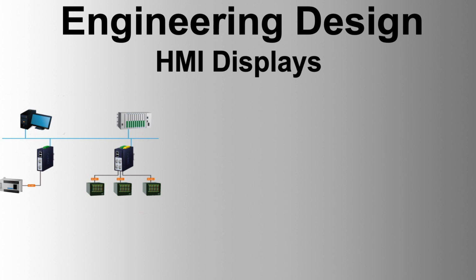Multivariable control loops show schematic views of multivariable control schemes, including process variables and tuning parameters for diagnostic purposes by technologists and control engineers. Sequence displays graphically represent control steps and their states for particular equipment. They include windows with sequence steps or guidance messages for operators during issues. IPF logic status. Schematic representation of IPF logic, displaying the status of individual IPFs and override facilities. First failure alarms are displayed, acknowledged, and reset here, and the logic status is used for trip analysis and troubleshooting.